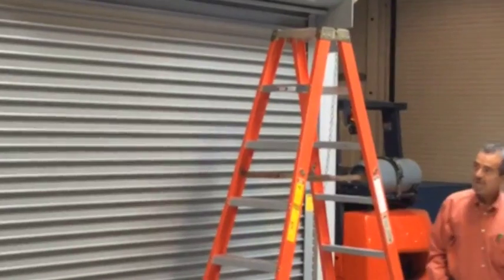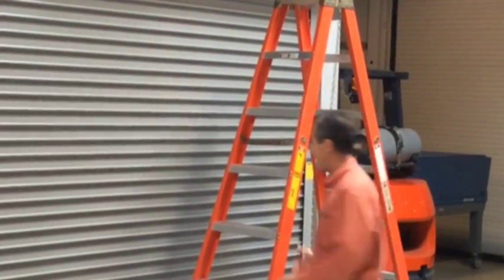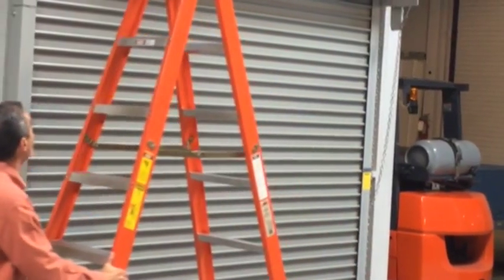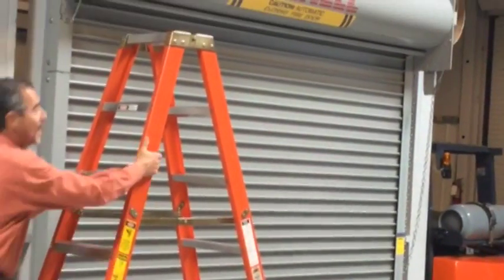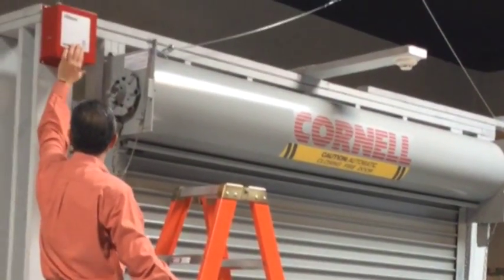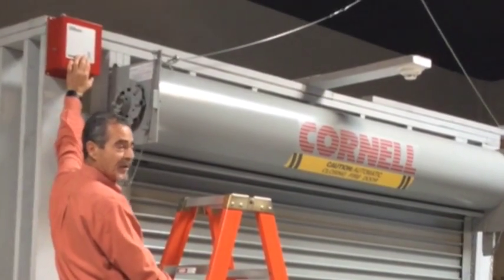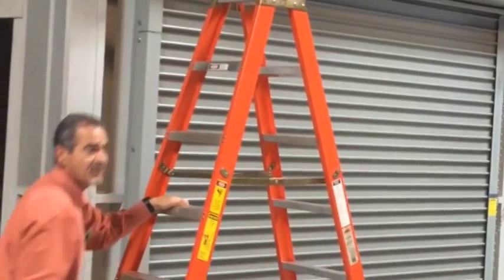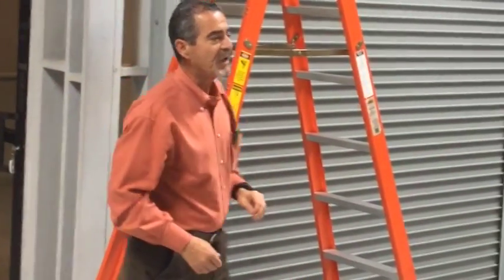Alright, so this would constitute a test. The door closed fully and all the way to the ground. It also closed within the required time period — no faster than two feet per second.